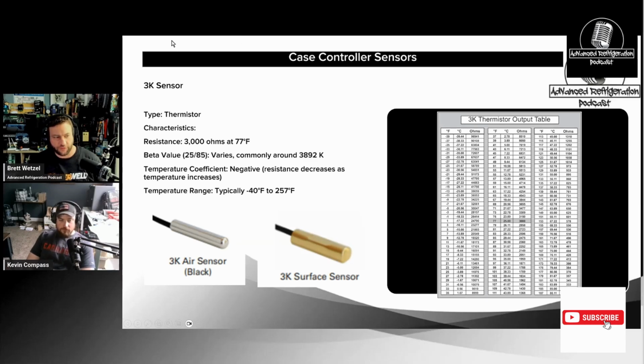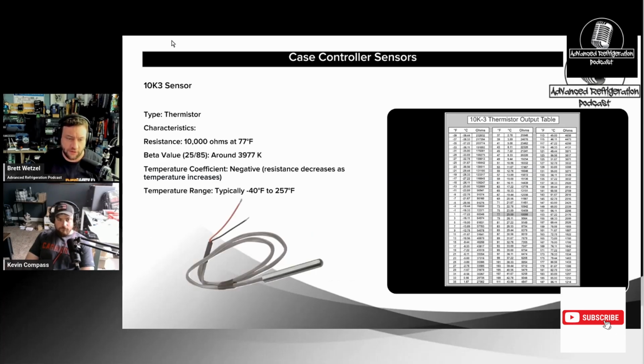I usually get the combo set where you have, for service, the small Fluke meter and the amp clamp that comes together. The amp clamp is going to measure that high resistance, but the Fluke meter will too. A lot of the Fieldpieces, the resistance doesn't go high enough - like PT1000, definitely. But if you're talking about something like the 10K3 or 10K2, a lot of times it doesn't have the resistance value it needs, so you're gonna have a tough time troubleshooting this properly.